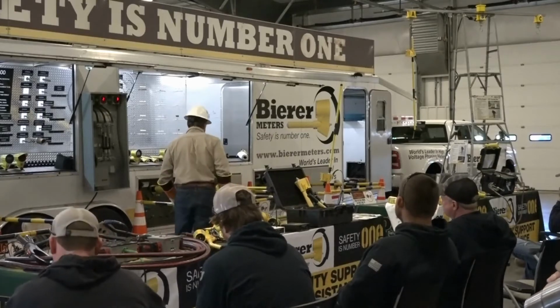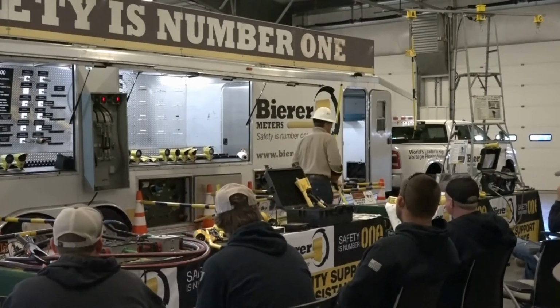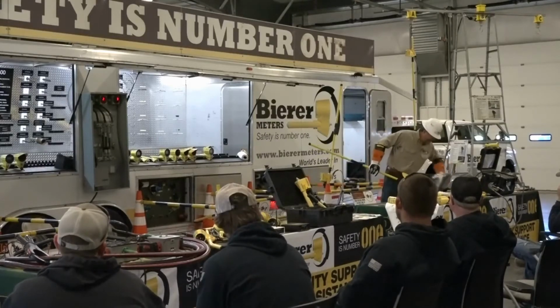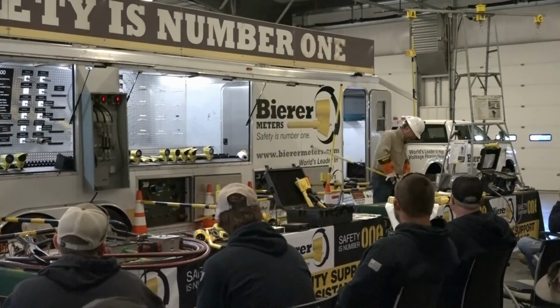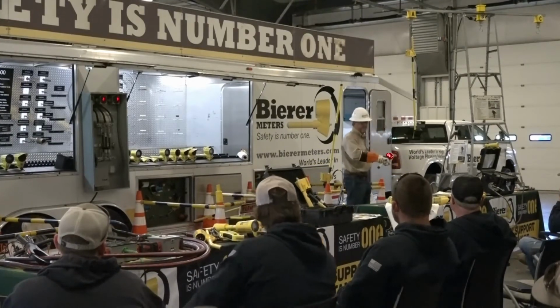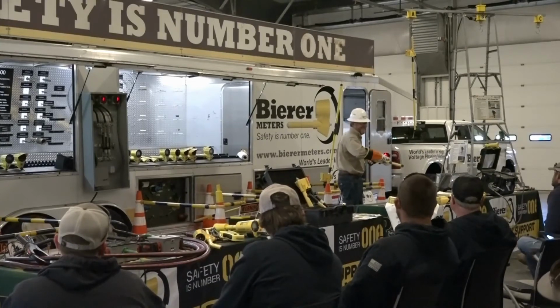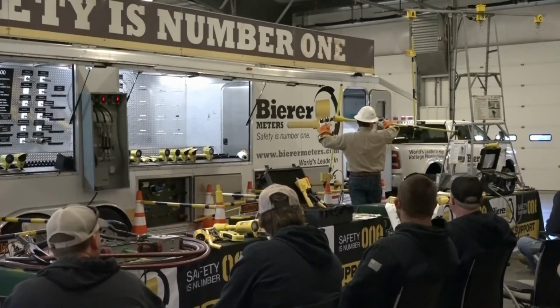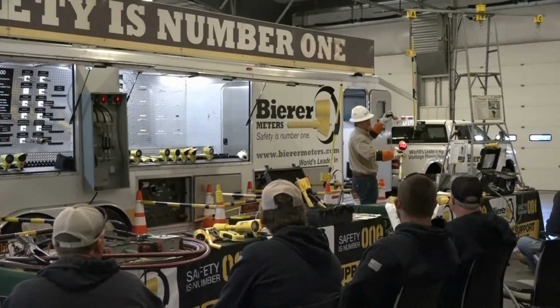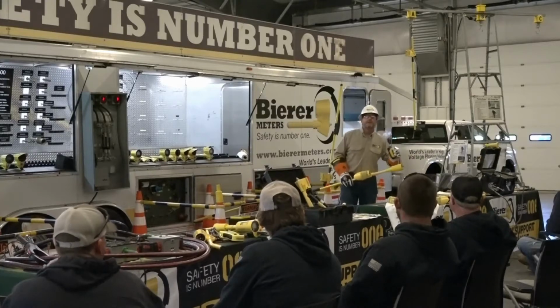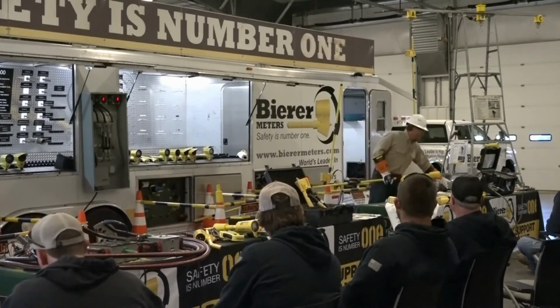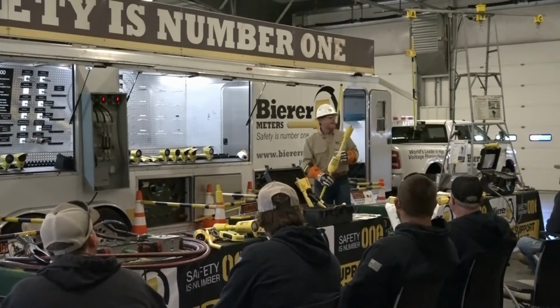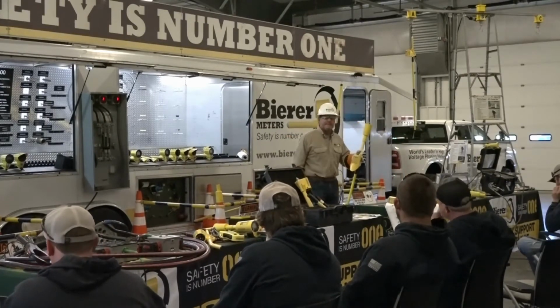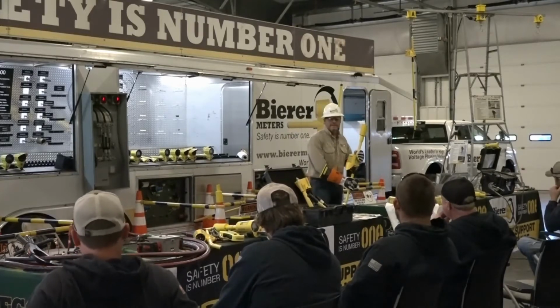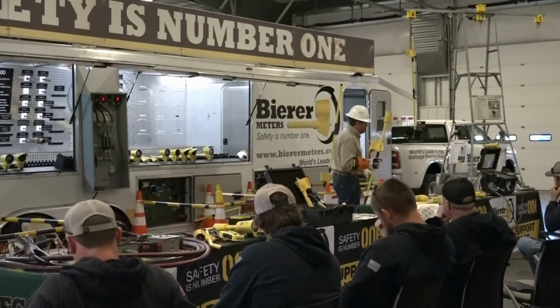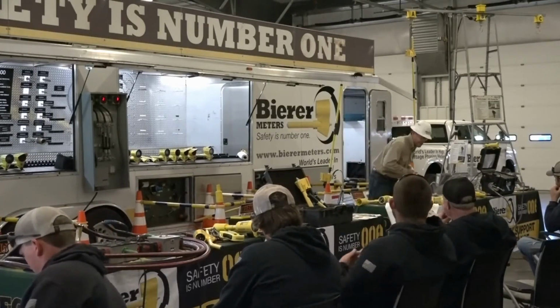So what we're going to do is test the tester on a live known voltage source. We've got a 3 kV power supply and a handheld power supply right here. Test the tester — you all see that, working right? Now we're confident this is a live known voltage source. Not a lot of current, high frequency, works great, very safe. We're confident our tool was working properly, so we can go ahead and set our EPZ. Very safe, and it's important — this is how we should be working. Any questions so far? Good so far?